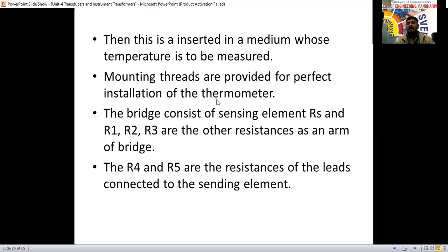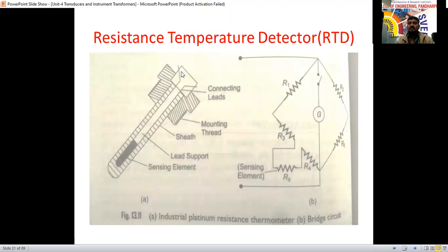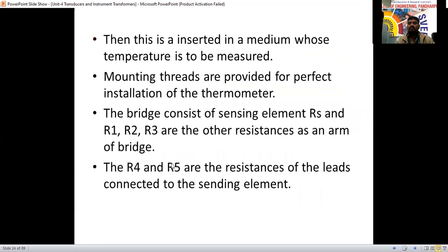Based on that, we have drawn the RTD equivalent bridge in the circuit diagram. The bridge consists of the sensing element resistance, called RS, and R1, R2 and R3 as the other resistances, the arms of the bridge. R4 and R5 are the resistances of the leads connected to the sensing element, and we connect the sensing element where it is needed.